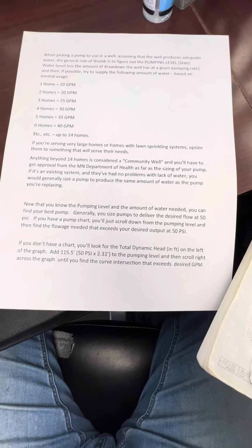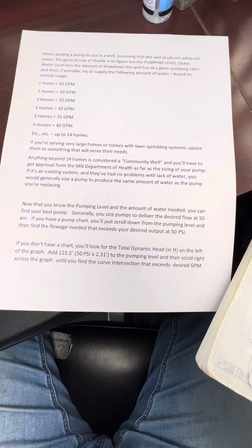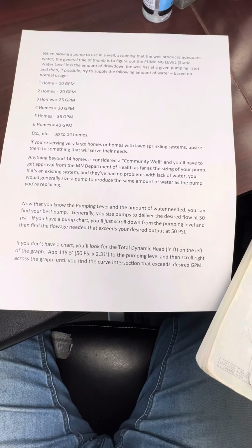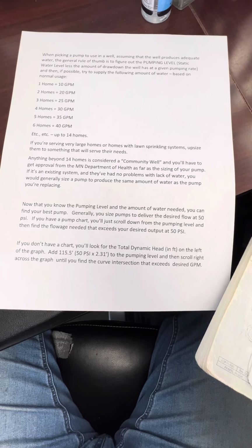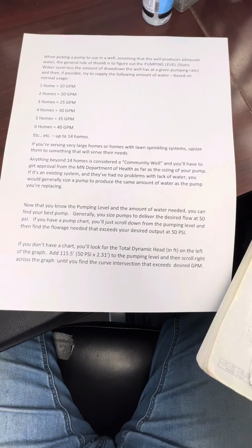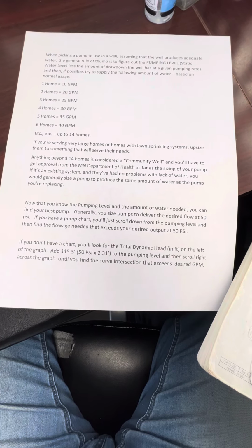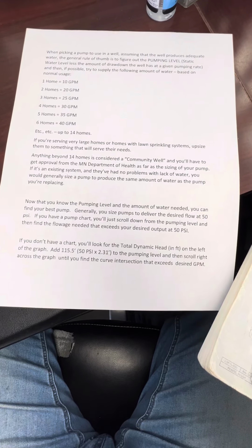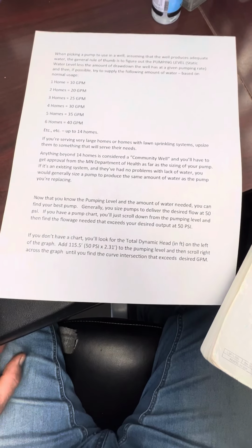If you don't have a chart and you've got a graph, then you look for the total dynamic head in feet on the left of the graph. So you add 115.5 to the pumping level. 115.5 is 50 psi times 2.31, so 1 pound of pressure equals 2.31 feet.